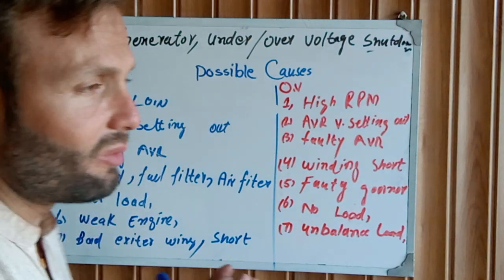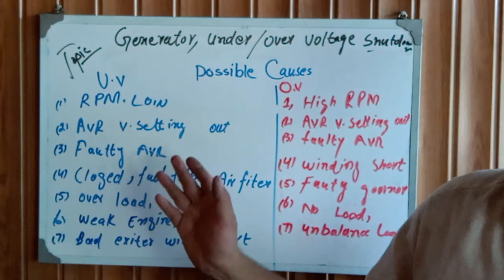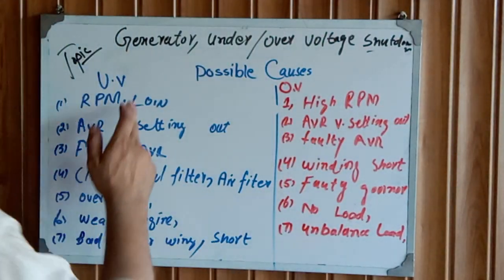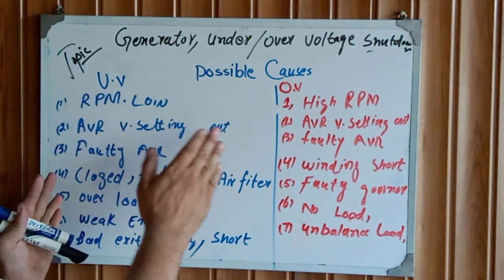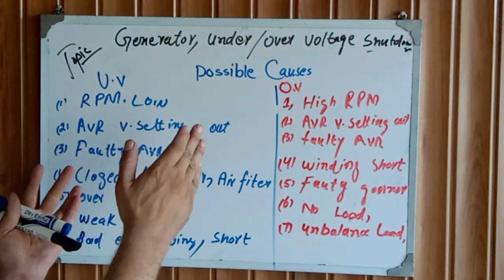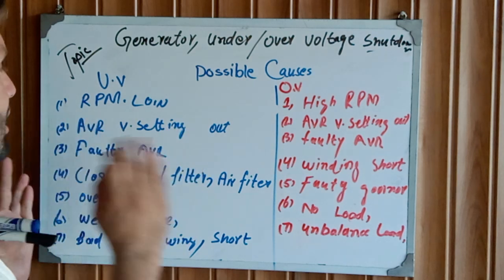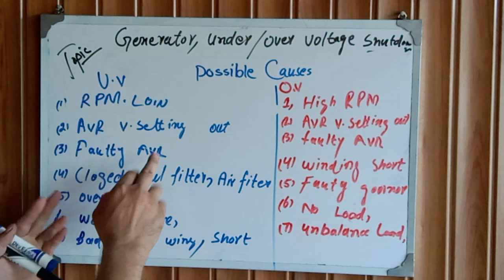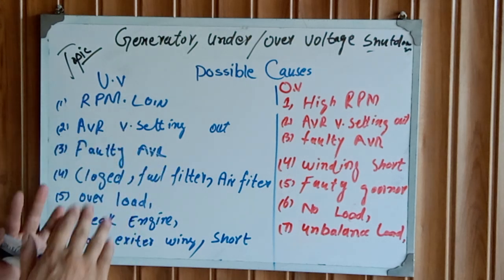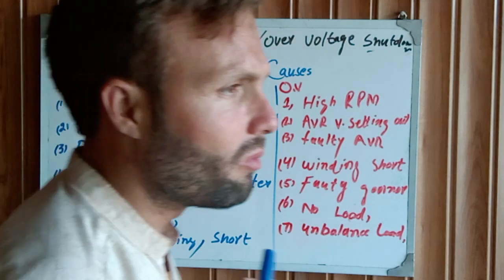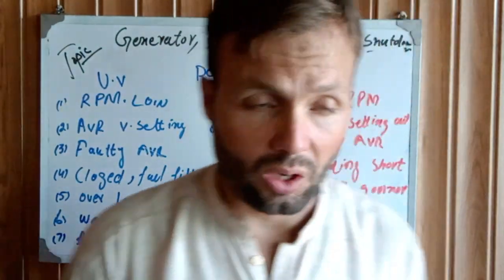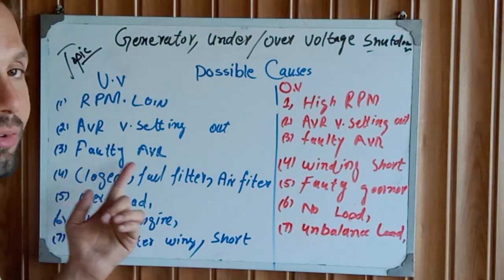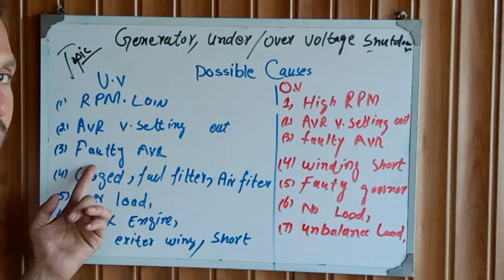Another possible cause is a faulty AVR. If your AVR is faulty or malfunctioning, this will be the main cause of under voltage. Even if your RPM is good at 1800 and your voltage looks correct after setting, if the AVR is malfunctioning it will cause the engine to shut down repeatedly. In that case, swap out the AVR — replace it with another one and check again.